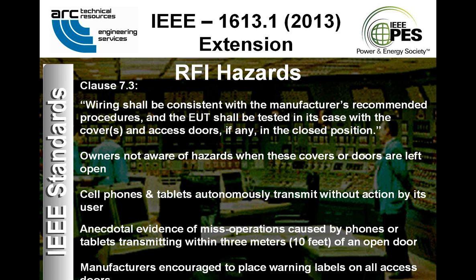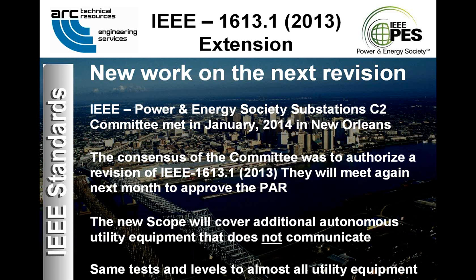There's new work planned for the next revision to 1613.1, which was just finished in 2013. The IEEE Power and Energy Society Substation C2 Committee met first in January in 2014 in New Orleans. They met again recently. Consensus of the committee was to authorize a revision of 1613.1 that we had just finished, rather than make it into .2 or .3 or .4. So it will be another 1613.1, and they're going to expand the scope, which I believe we've just received, to cover additional autonomous utility equipment that does not communicate. This would be like capacitor bank controllers and tap changer controllers and data storage devices, displays, etc.